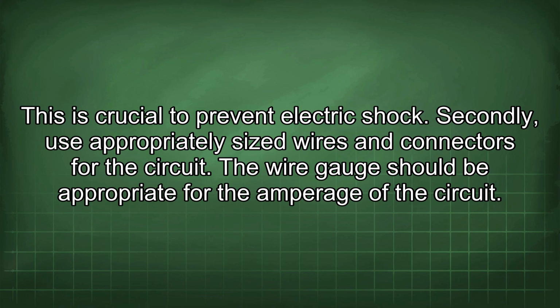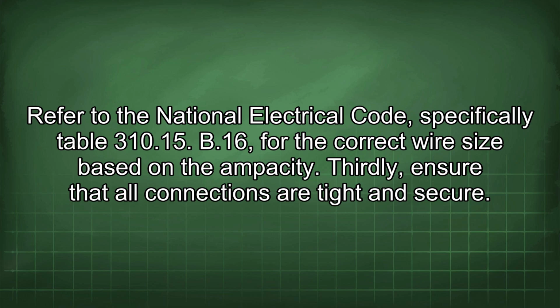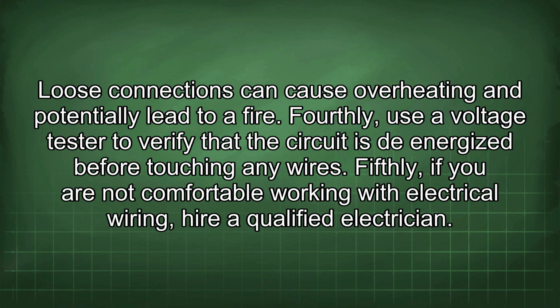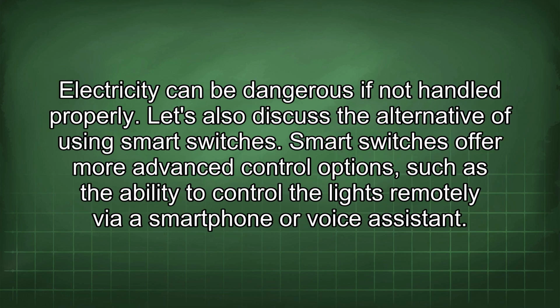Secondly, use appropriately sized wires and connectors for the circuit. The wire gauge should be appropriate for the amperage of the circuit. Refer to the National Electrical Code, specifically Table 310.15(B)(16), for the correct wire size based on the ampacity. Thirdly, ensure that all connections are tight and secure. Loose connections can cause overheating and potentially lead to a fire. Fourthly, use a voltage tester to verify that the circuit is de-energized before touching any wires. Fifthly, if you are not comfortable working with electrical wiring, hire a qualified electrician. Electricity can be dangerous if not handled properly.